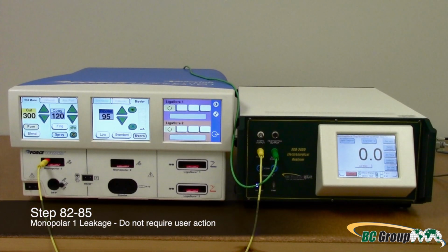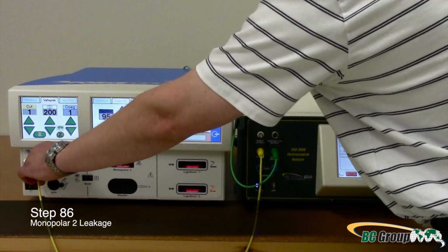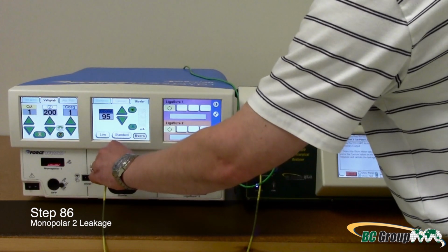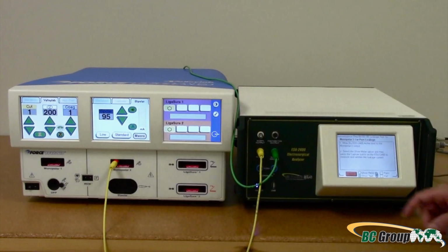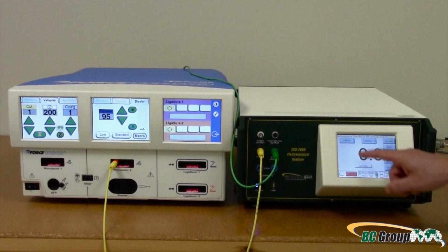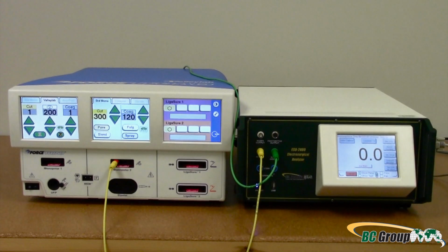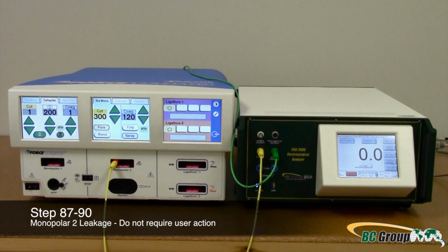Steps 82 through 85 do not require user action. Step 86. Monopolar 2 leakage. Move the ESU-2400 active lead to the Monopolar 2 output. Select Show Meter and then press Capture. Steps 87 through 90 do not require user action.